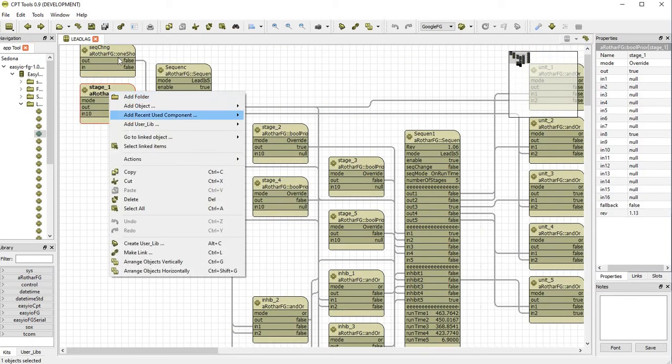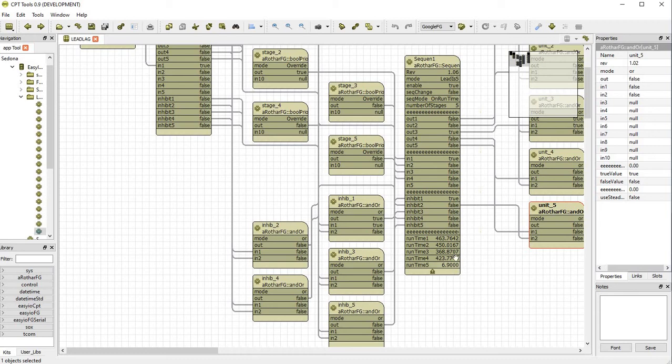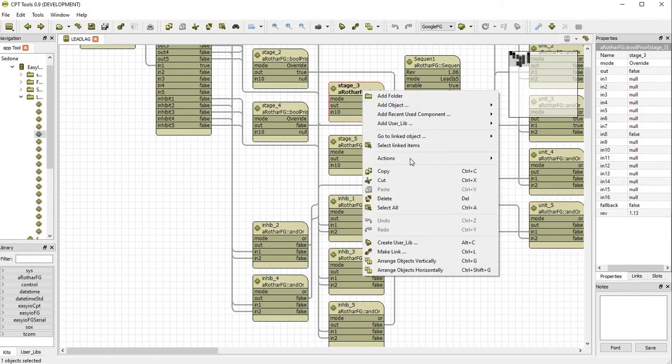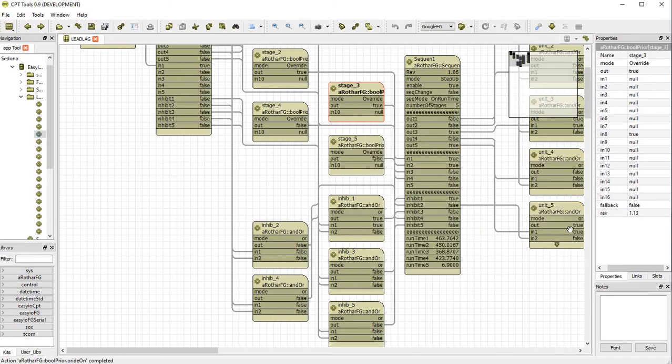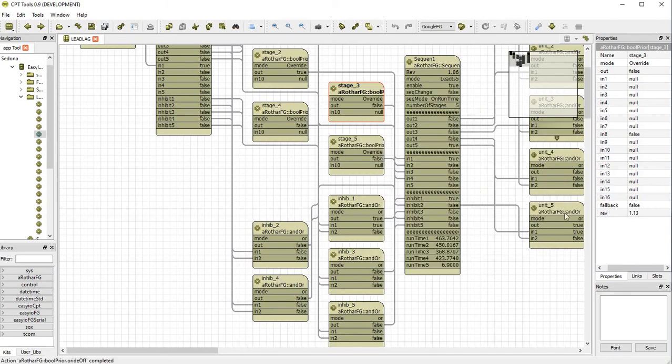So in this case we'll go from 5, sorry, wrong block again. So 1 becomes the lead chiller or lead equipment, 3 remains running, 5 remains off, because even though it has the least amount of run hours, that's not what was keeping the unit running. If we had a step or stage increase, 5 then becomes on, 3 is on. If we then step down, 3 is off, 5 remains on based on its runtime.